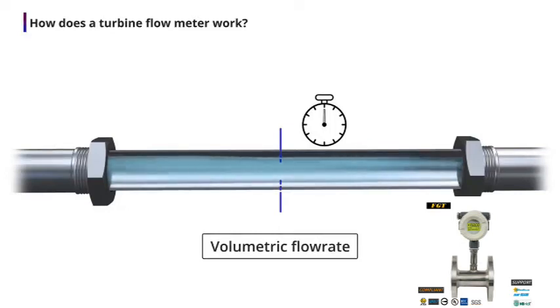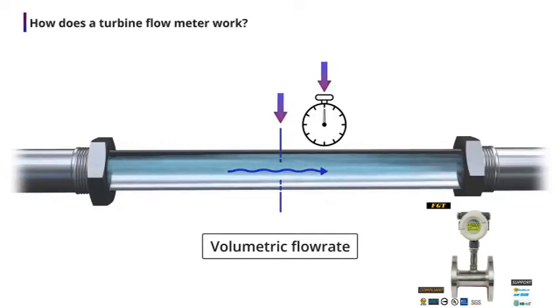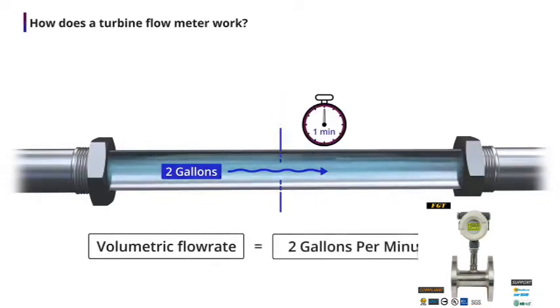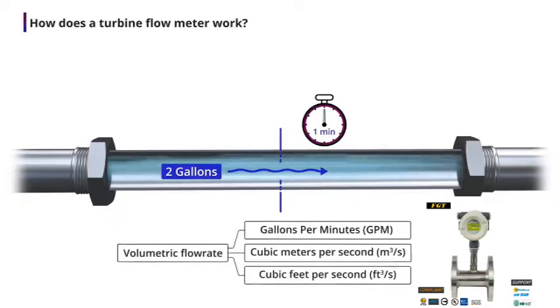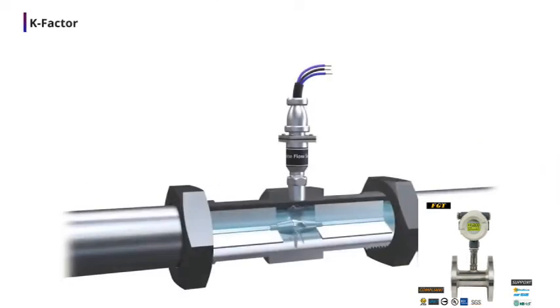Volumetric flow rate indicates the volume of fluid that passes a point in a unit period of time. If you could count the number of gallons of liquid flowing past a certain point in 1 minute, you would be able to state the volumetric flow rate. Volumetric flow rate is expressed in units such as gallons per minute, or GPM, cubic meters per second, and cubic feet per second. Okay, so now we've reviewed fluid velocity and volumetric flow rate. Let's talk about how a turbine flow meter is used to measure volumetric flow rate.